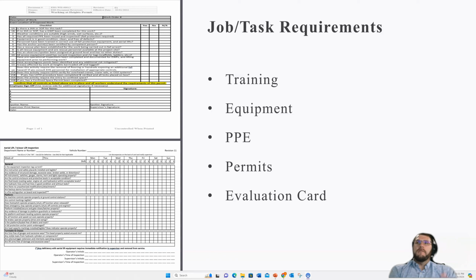You're also going to have your Fall Pro harness, your dual self-retracting lifelines, tool tethers, arc-rated clothing, as we already talked about, 4-cal rated. Your balaclava obviously is going to be 12 calorie, and your face shield also is going to be 12 calorie or 10 calorie, whatever the standard is right now. Shock-rated rubber gloves, with protectors, are going to be required for shock protection.